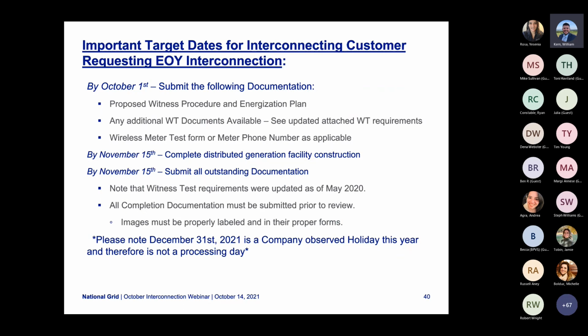Moving quickly here, next one, JJ, this one's for you: if a customer has a PV system with a 61 kW AC inverter nameplate and is also locating significant DC-coupled storage on site, installing UL 1741 SA inverters with a UL 1741 listed power control system, can they apply for 50 kW AC interconnection through a 50 kVA single-phase transformer if the PCS is programmed to not allow 50 kW AC to export to the grid?